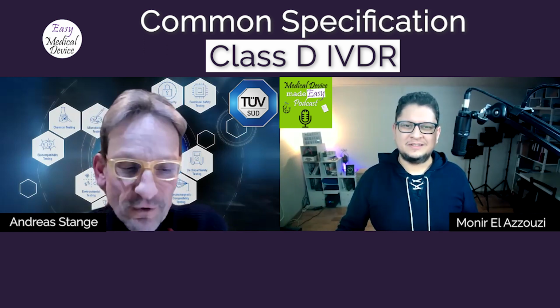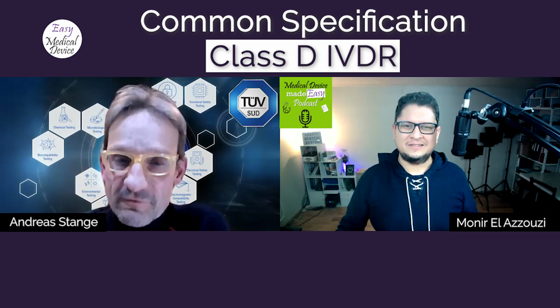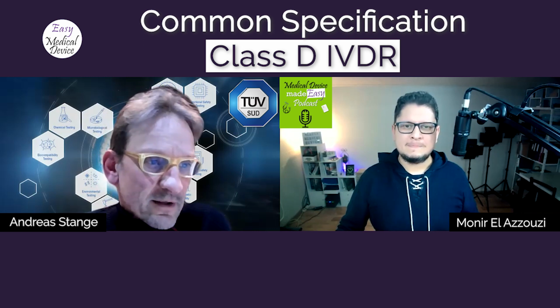Oh, yeah, that's a good question. No, it was not coming out of the blue. We were waiting for that. And when we look at the rolling plan, the common specification publication was expected quite some time earlier already. Why is this so important? Because without them, as I explained, you have to go through the expert panels. The expert panels were also just established in September last year. So before that, there was basically no way to certify a Class D device under the IVDR.